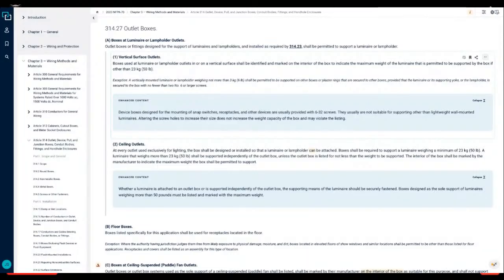And then it says the box must be listed for not less than the weight to be supported. So when you look at this, they're telling you that you're using the box as the outlet for your lighting fixture. Period. There's no disagreement on that.